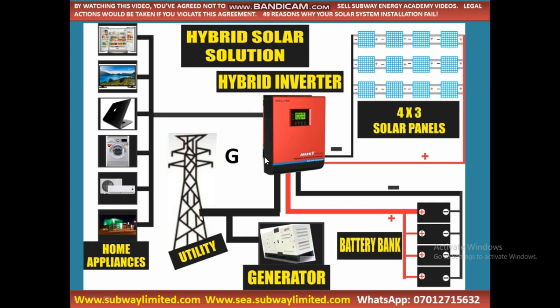But the issue is, if you design this system as a hybrid solution, and later the utility gets issues, the generator gets issues, remember you did not properly size this system as a standalone - you designed it as a hybrid setup. If these two power sources get issues and it's only the panel giving the needed power for charging the battery, and the client doesn't communicate with the professional, or the professional doesn't call the client to ask about the system's performance, this system will get issues within the shortest possible time, because it was not designed as a standalone system. That is how the type of system affects the design, and also contributes to failure of solar system installation.